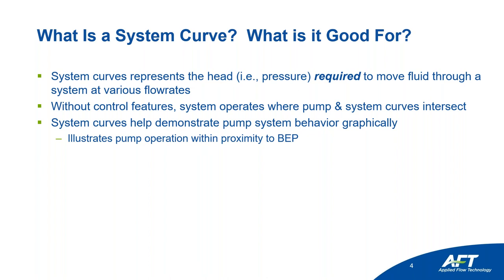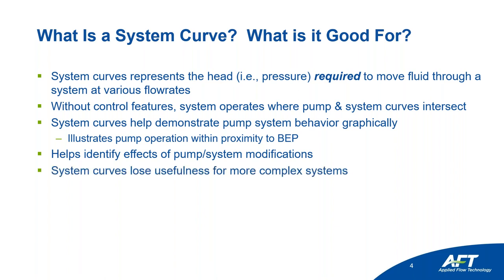The further away you get from your best efficiency point, the more reliability problems you're going to start having in your system. So this is where it's key to understand system curves and how they're generated, and the situations where they may be a little bit ambiguous. When you look at a pump and system curve together, it can help identify really quickly how various pump or system modifications are going to affect your pump operating point.